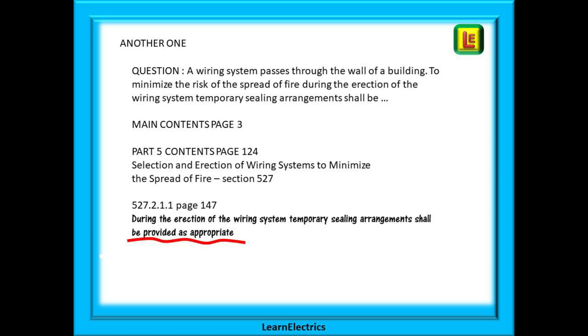Another question. A wiring system passes through the wall of a building to minimize the risk of the spread of fire during the erection of the wiring system temporary sealing arrangements shall be. So find the Part 5 contents page on page 124. Here we find selection and erection of wiring systems to minimize the spread of fire section 527 and there is regulation 527.2.1.1 on page 147. The answer is sealing arrangements shall be provided as appropriate.